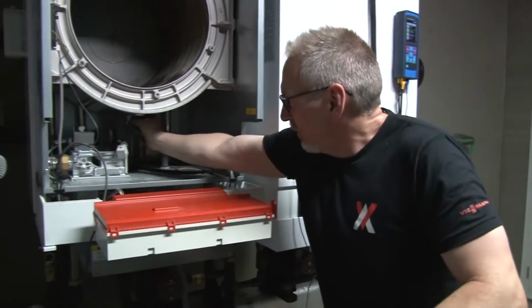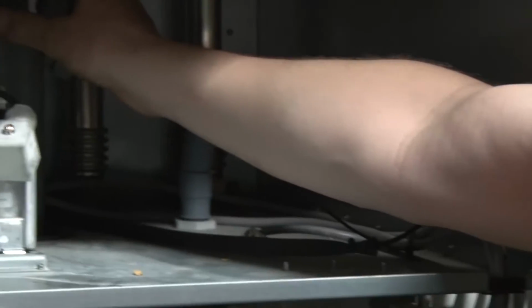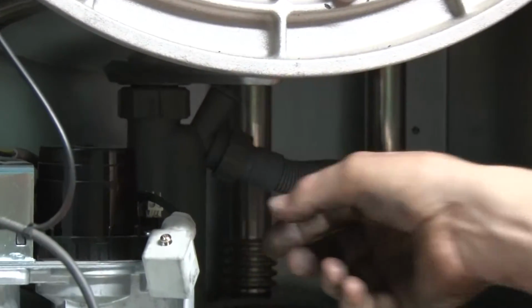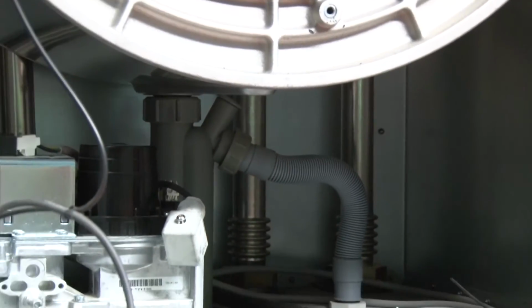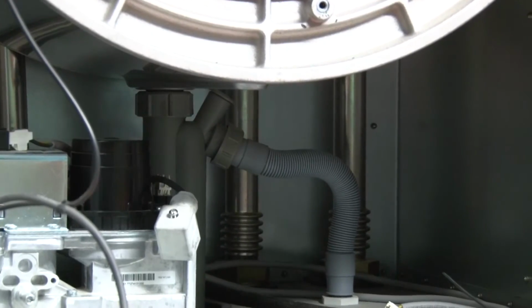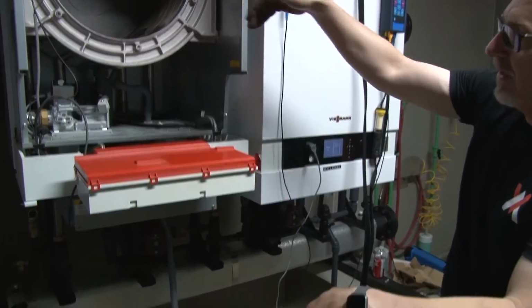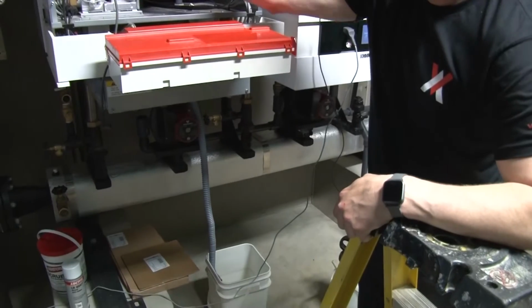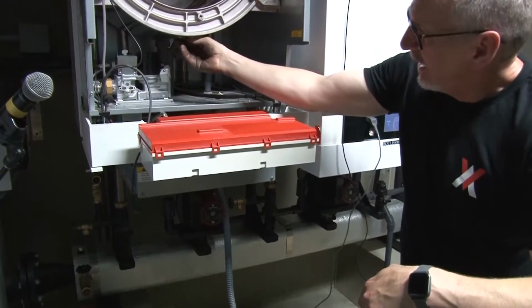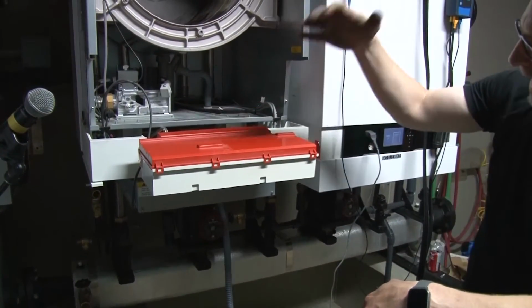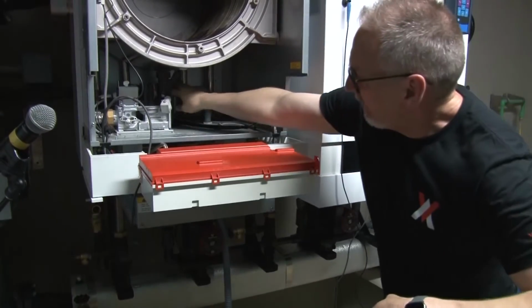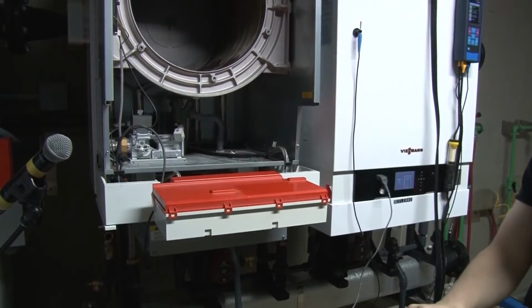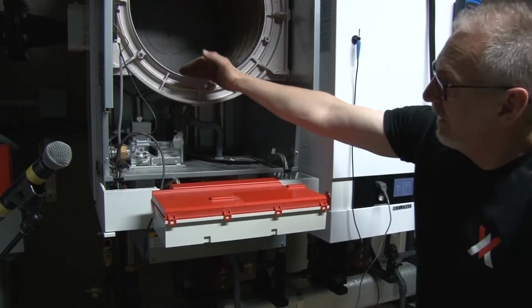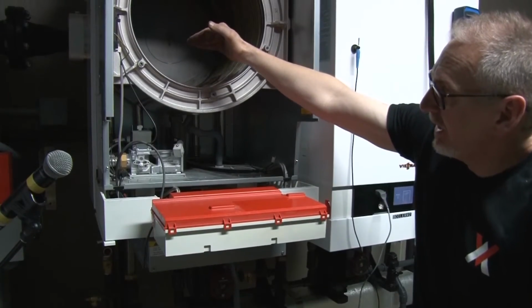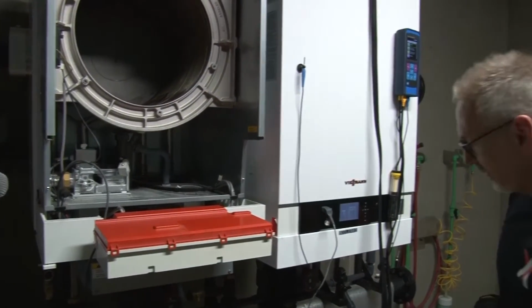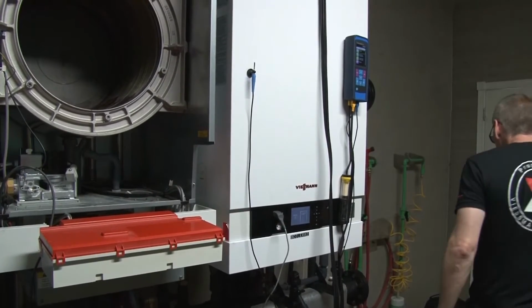I would also, at this point, remove the P-trap and put a hose or something on it and take it down to a drain. So what we're going to do here is a little bit backwards. Once I get that debris kicked out of there, it's sitting at the bottom of the heat exchanger now. I need to get that flushed out. Otherwise, when I start the boiler up, it's going to go down with the condensate and it may plug up my P-trap. And then of course you're going to have that condensate back up in the heat exchanger and end up with some sort of a problem or fault. So we're going to wash this out.